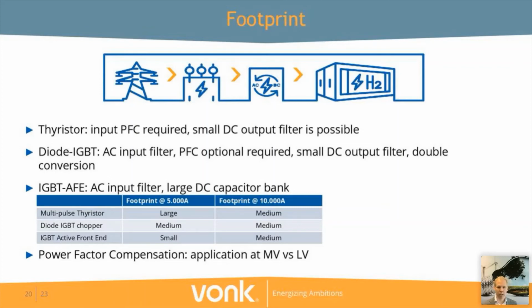When looking at power factor compensation, I already mentioned that applying it at low voltage results in a smaller footprint. However, applying it at medium voltage does give you some freedom at where to locate your power factor compensation units, because it can be anywhere at the medium grid, so you have a bit more freedom to play with, even though it requires more space.